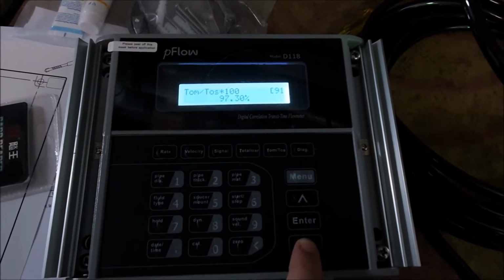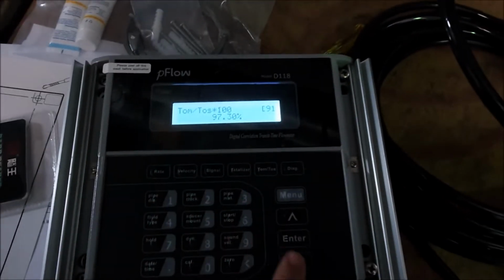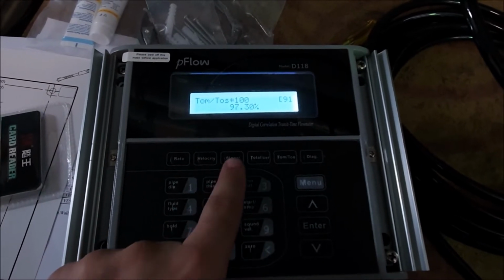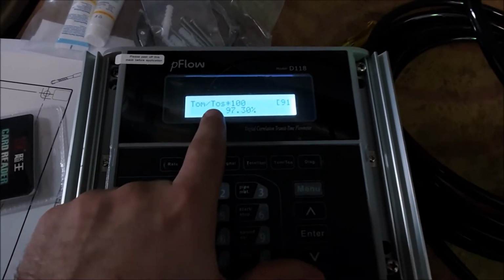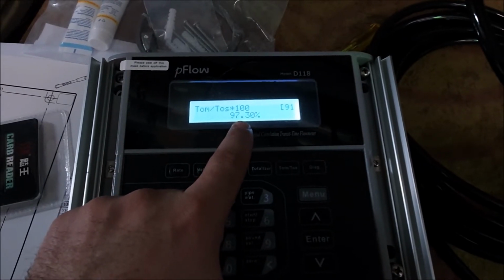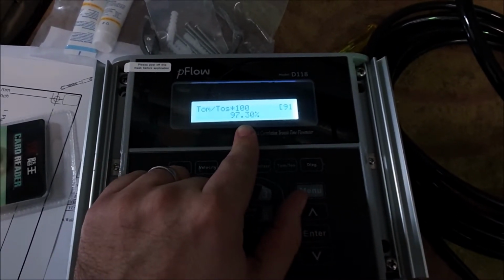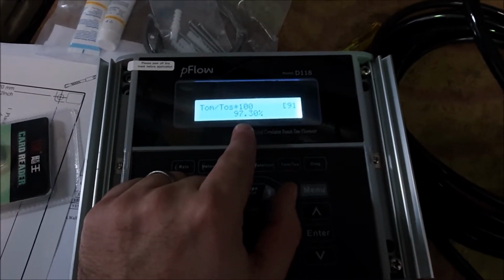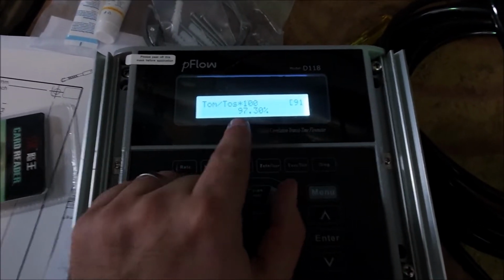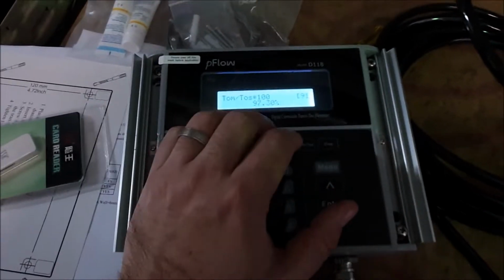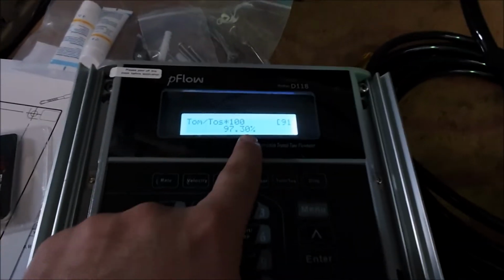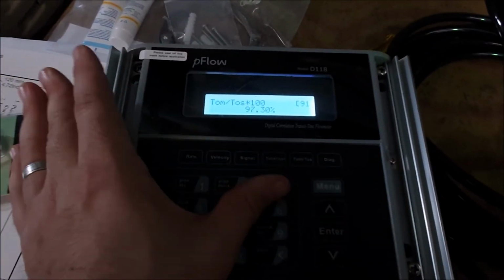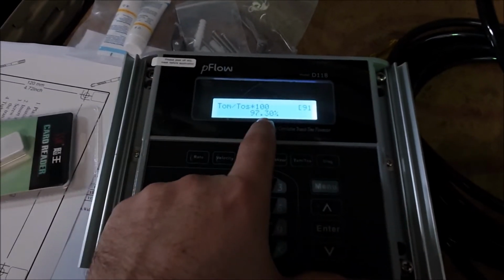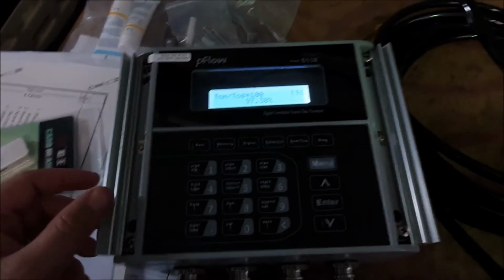Then the other one you want to look at is down a menu on menu 91. So quality is actually menu 90, or just the quality key. Menu 91 is a ratio. This one you need within 3% of 100%, so between 97% and 103%. If you're outside of that, then you may have bad installation, or maybe your spacing is incorrect, or something like that. So if I was to move the transducers left or right, or space them closer or further apart, this value would change. So we're good with 97.3, that's okay.